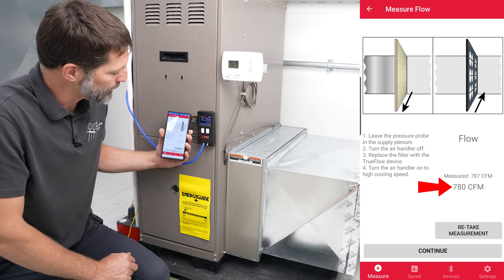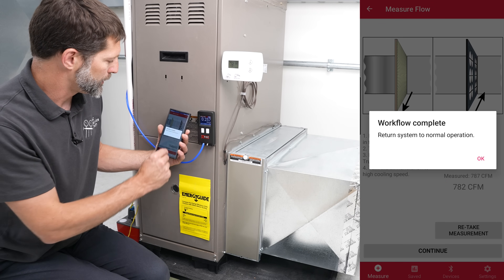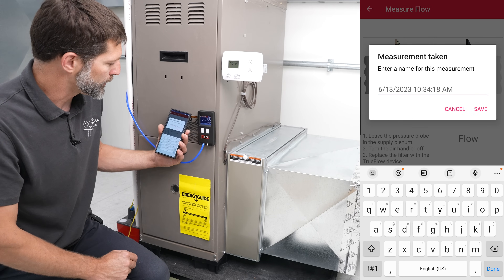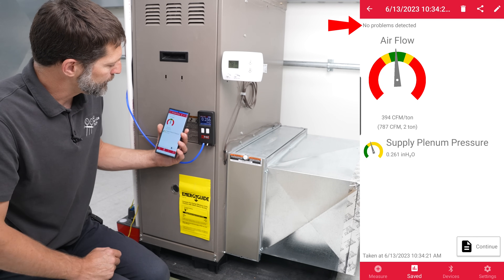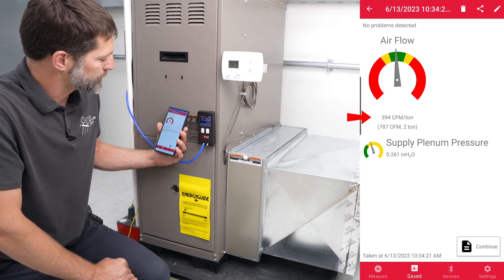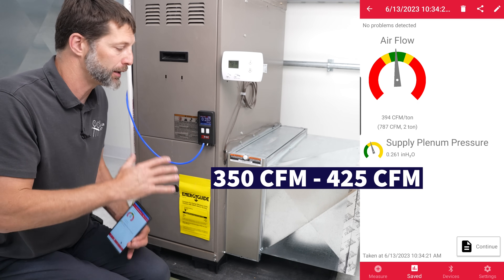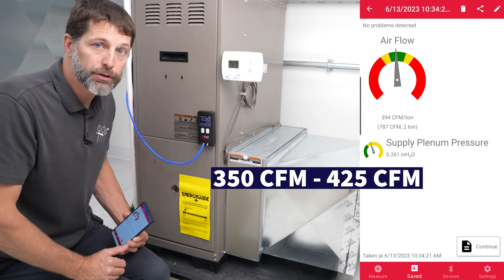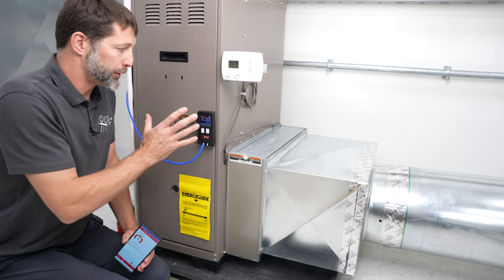You want to have the "air in" side facing where the air is coming in on the return, and we're using this weatherstripping to seal it up tight against the back. You can see a little lip here, but when we put the door on it should be pretty much sealed. Now we're going to turn the system back on in air conditioning mode and take our other measurement. It's pretty simple to use — it's saying that we have 780 CFM. Workflow complete, so we can just save it. It says no problems detected; airflow is about average at 394 CFM per ton. You want about 400 CFM per ton — maybe 350 to 425 depending on your desired dehumidification during air conditioning mode. That's how you measure airflow for CFM.